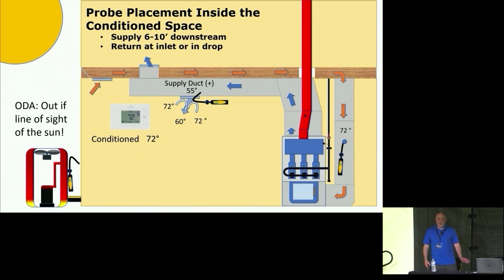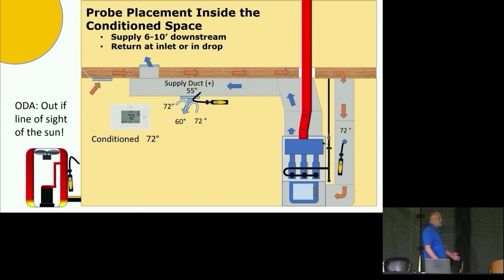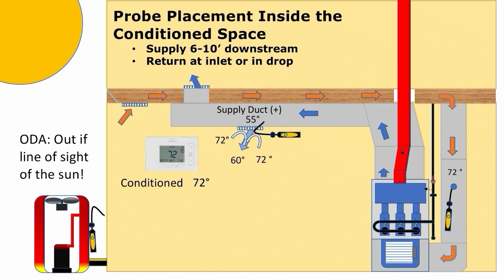If we're inside the conditioned space, there's two types of systems. We deal with a lot of stuff in our area which is inside the conditioned space. Duct leakage is not as big of a problem as you guys have in Florida when the ducts are outside the conditioned space.